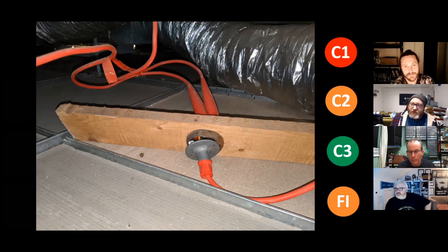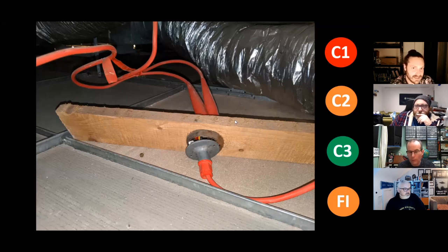So is it better to have your loop in separate conductors, not in one multi-core cable, where it could lose its integrity in one slice? That makes sense, and it depends, Dave, on what's on the other end. In some circumstances in heritage buildings, we have used a 4-core for a small loop with FP off MICC, but it's been noted in a drawing, agreed with the client, and risk assessed by a consultant, by the designer and everything else.